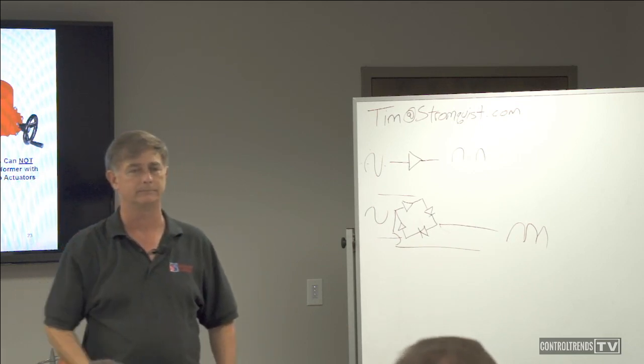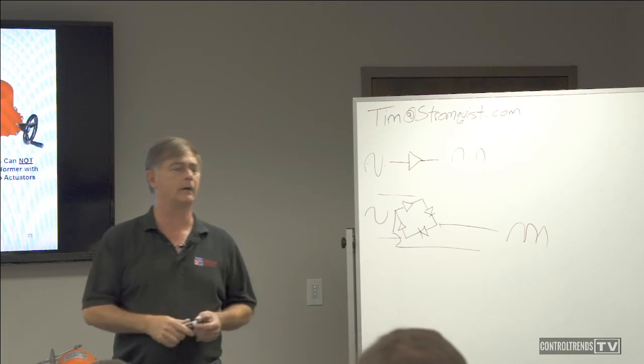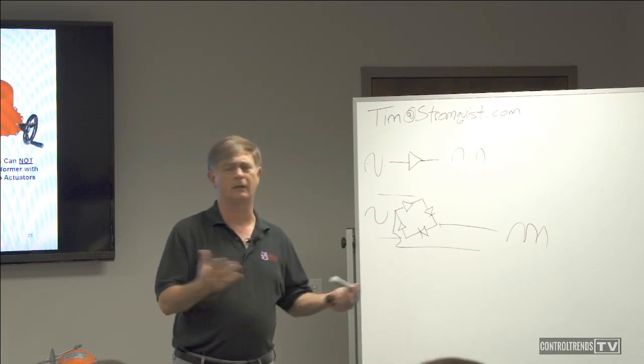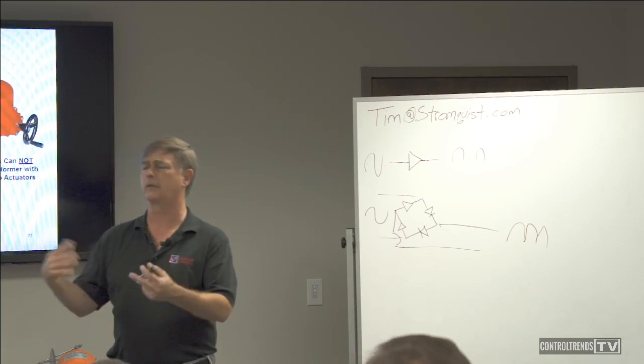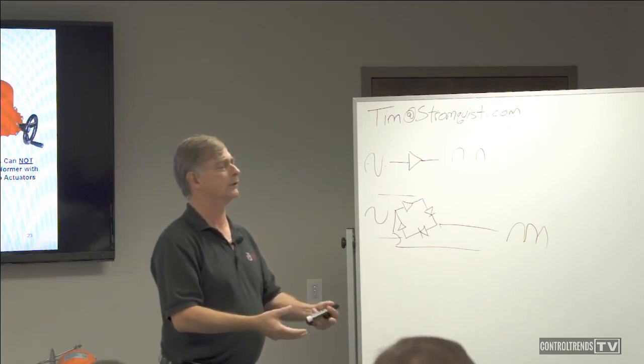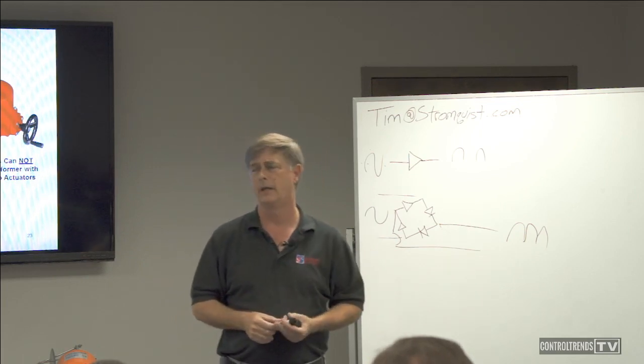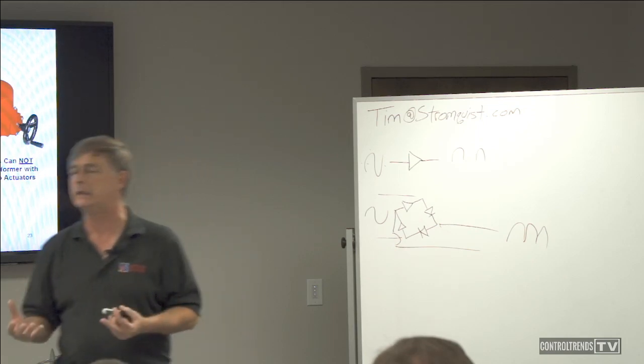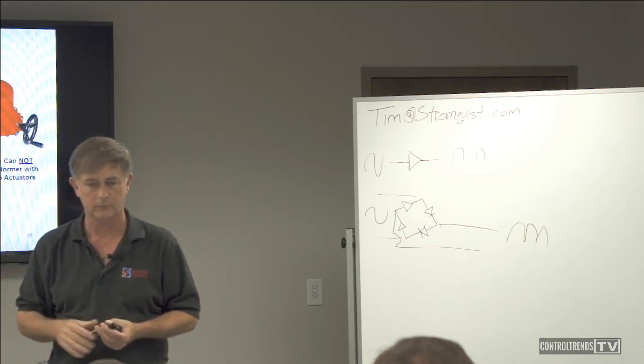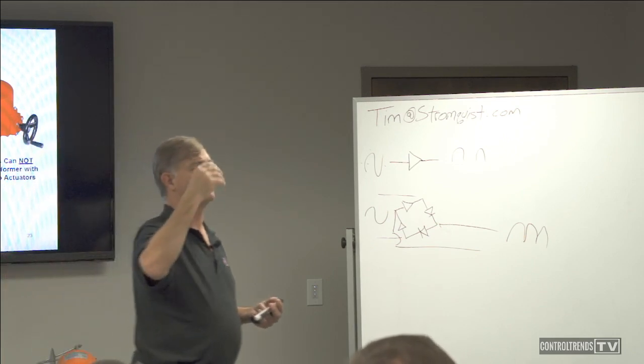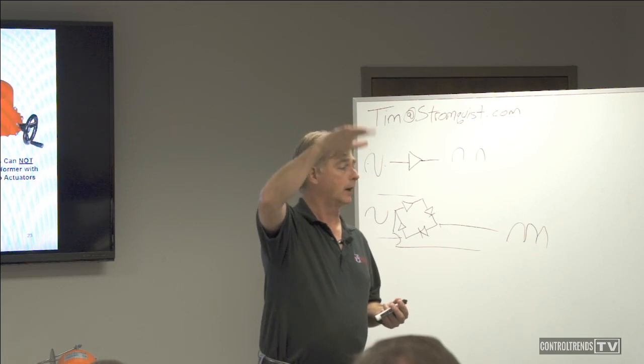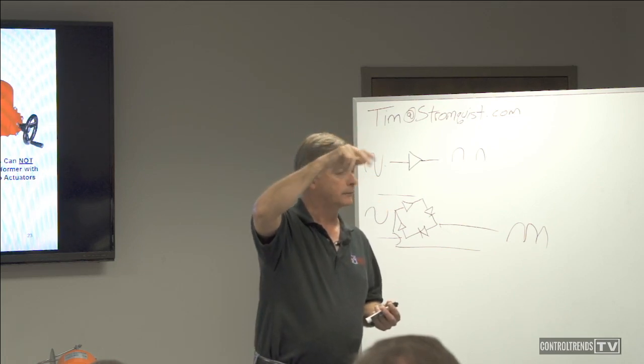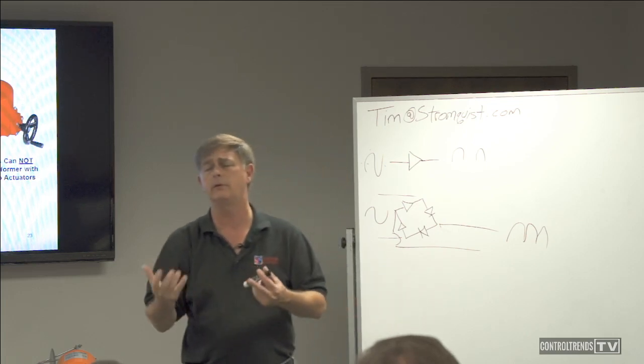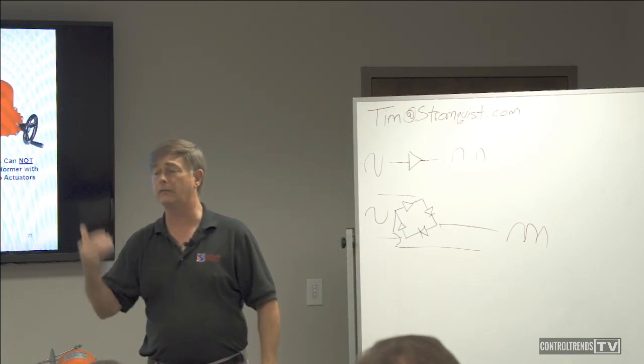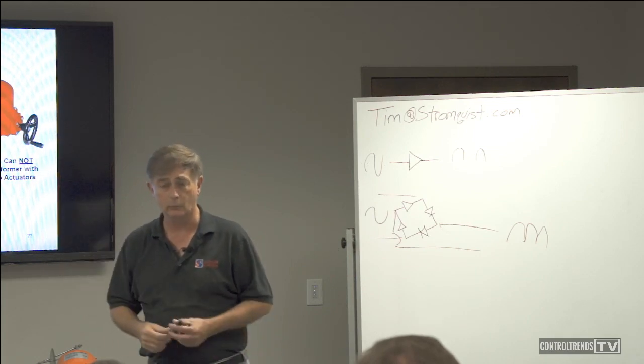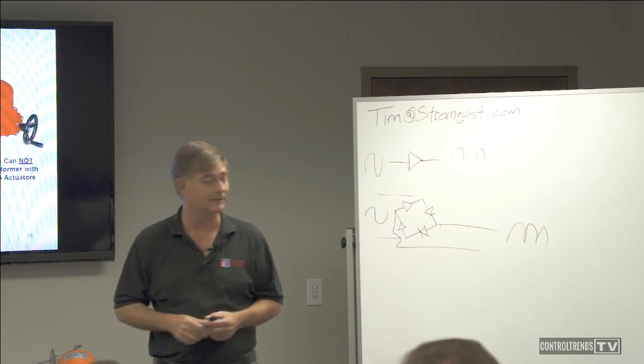Let me tell you a story. Got a customer who had an application in a lab. In this lab, they've got liquid nitrogen and liquid helium in canisters. What they wanted is, in the event of a leak, an exhaust fan to come on. And part of this, they wanted a VFD to control the exhaust fan. We wanted a certain minimum amount because we wanted to keep the room slightly negative. But in the event of a leak, we wanted this thing to ramp on up and take care of the leak.